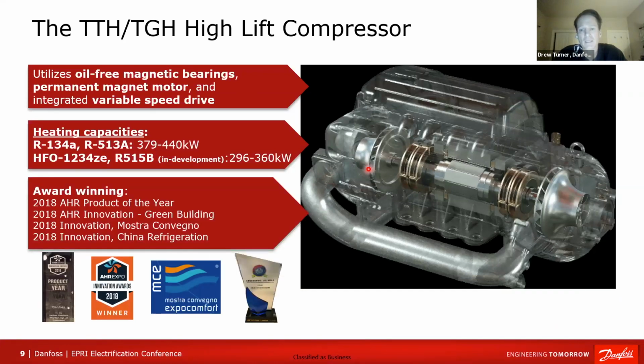And with the compressor, it's important to also talk about the forces that you're managing. So with the high lift compressor, what you're trying to manage is higher forces for the heat pump applications. And with those higher differential temperatures and pressures, managing those forces is a little more complicated with the magnetic bearing design where you have no contact. So again, it all ties together.